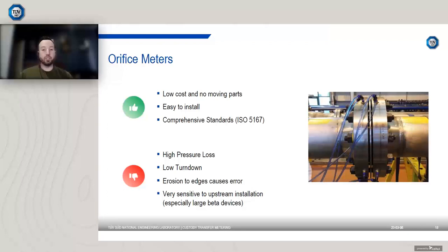And another disadvantage is they're very sensitive to upstream installation effects. So if you don't have a nice, fully developed flow profile going into the meter, let's say you've got swirl from bends or a partially closed valve, that's going to affect the meter performance.